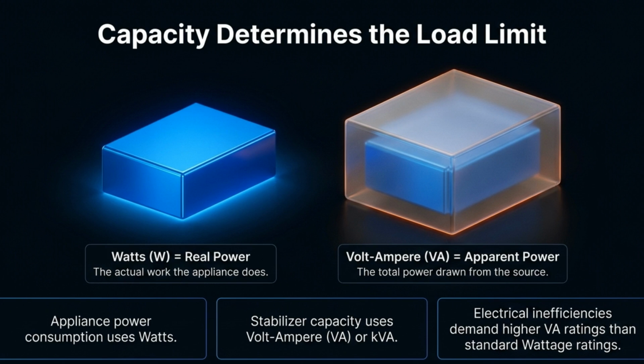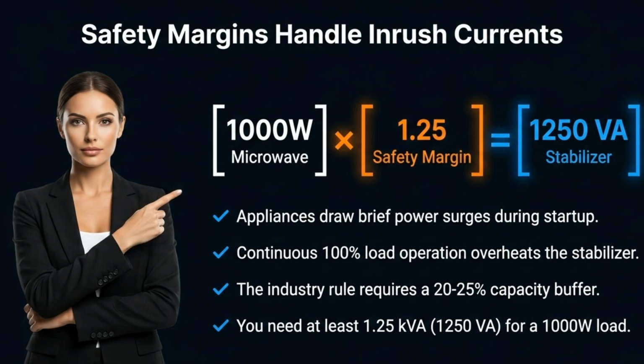Capacity determines the load limit. While appliances use watts, stabilizers are rated in volt-ampere, or VA. Electrical inefficiencies mean that the VA rating must be higher than the standard wattage. To handle inrush currents during startup and prevent overheating, always include a safety margin. Industry rule requires a 20 to 25% buffer, meaning a 1,000-watt load needs at least a 1250 VA stabilizer.